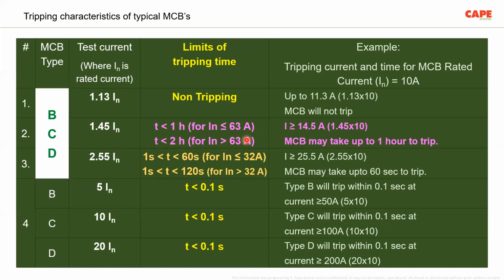It means in a 100 amps circuit, if the current is about, let us say, 140 amps, and you are using an MCCB, up to 140 amps for 2 hours, your circuit and the connected load are supposed to withstand it, basically. So we should select and erect the wires in that particular fashion. The installation must withstand that much current and that much duration. If the current is greater than or equal to approximately 2.55 times, then an MCB of up to 32 amps trips within 1 second to 60 seconds.